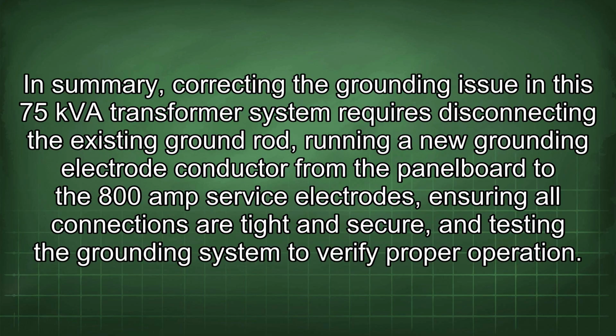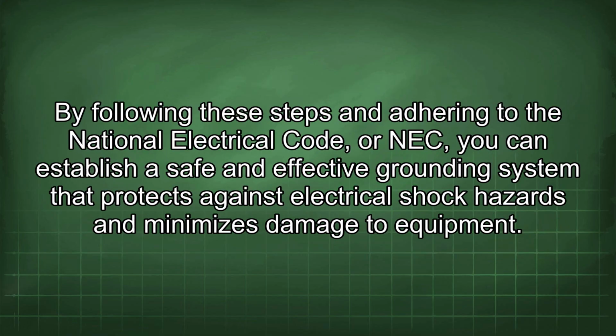In summary, correcting the grounding issue in the 75 kVA transformer system requires disconnecting the existing ground rod, running a new grounding electrode conductor from the panel board to the 800 amp service electrodes, ensuring all connections are tight and secure, and testing the grounding system to verify proper operation. By following these steps and adhering to the National Electrical Code, or NEC, you can establish a safe and effective grounding system that protects against electrical shock hazards and minimizes damage to equipment.